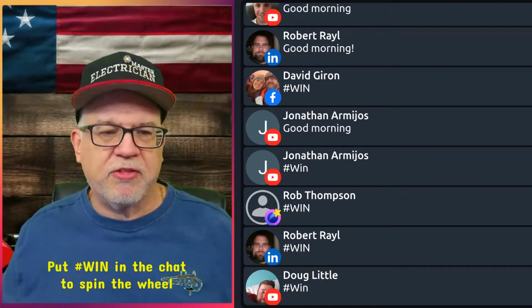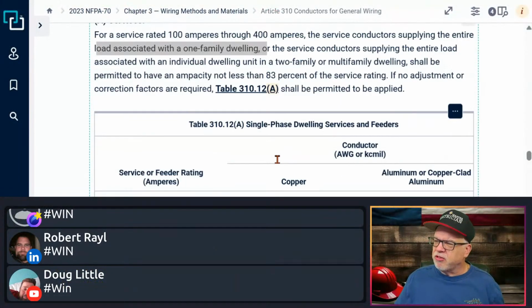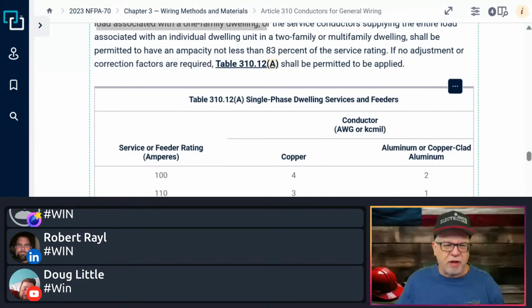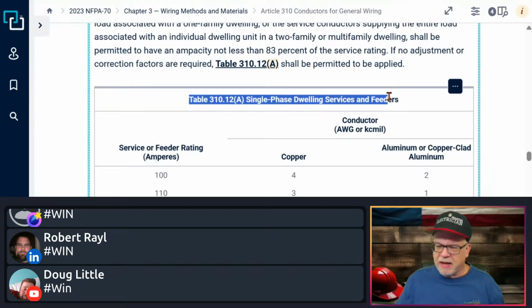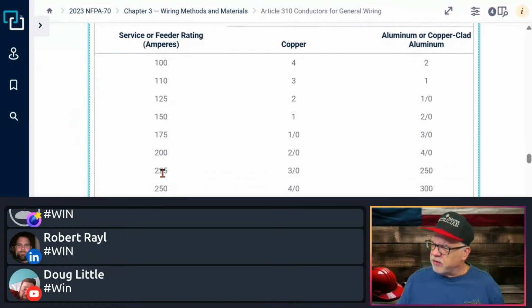Now, if you're going to use the NEC here, and there are no correction or adjustment factors involved, then you just pull straight from this table. And this table's been added back to the code. Previously, it was back in the informative Annex D examples, right? But it's made it back now for 2 cycles. It's been in 310.12. So here, if it's 200 amp, boom, right here. If that's what the service or feeder rating is, then it's a 2-aught copper or a 4-aught aluminum. And that's probably what y'all buy anyway. For a 200 amp, you'll probably use aluminum.